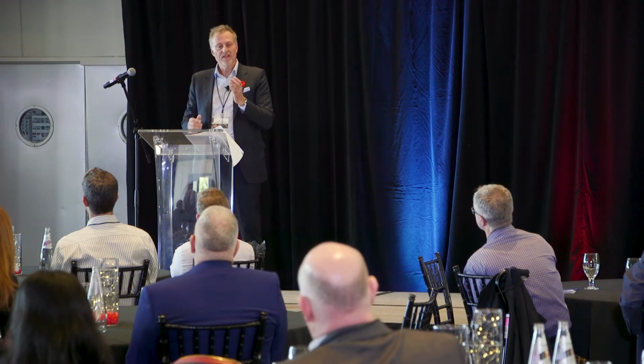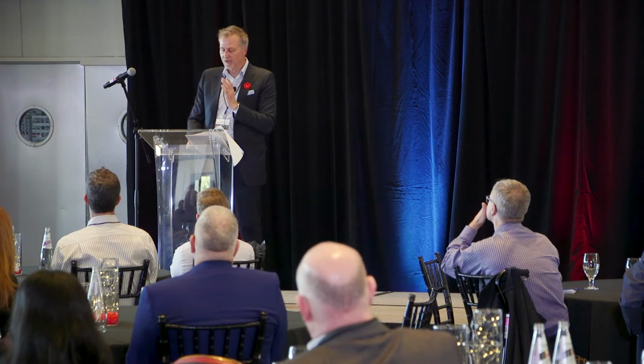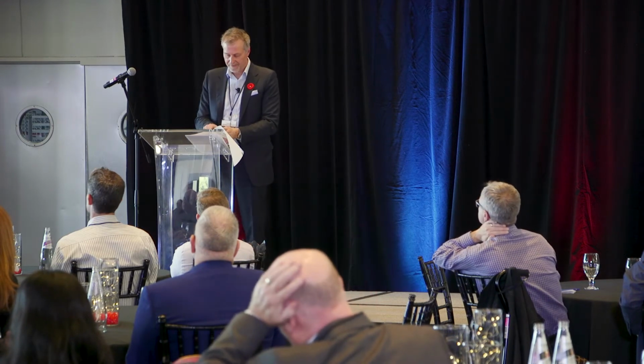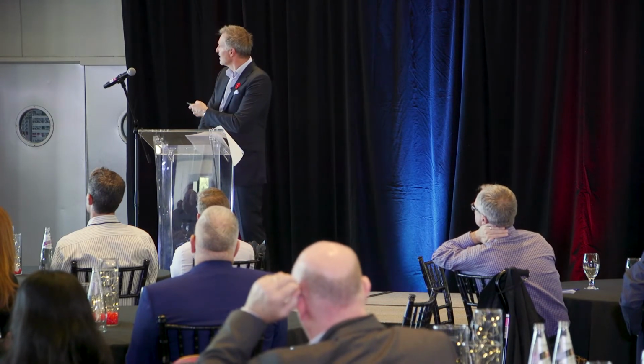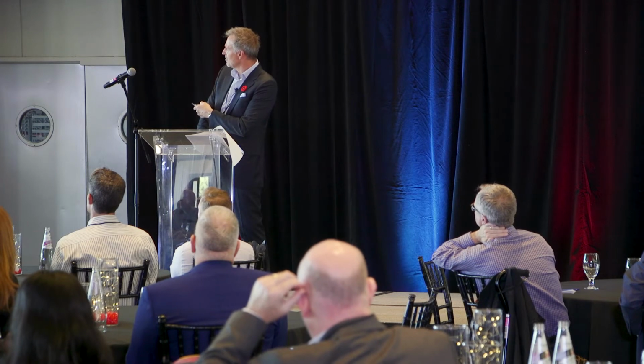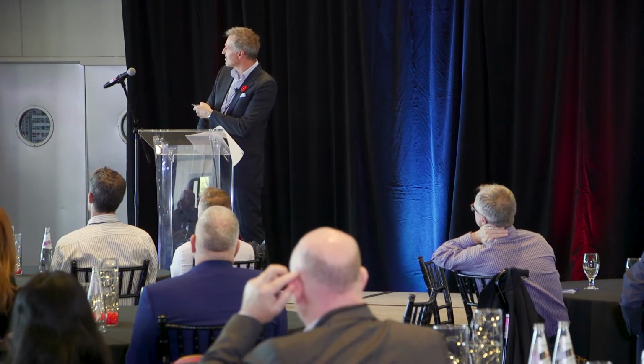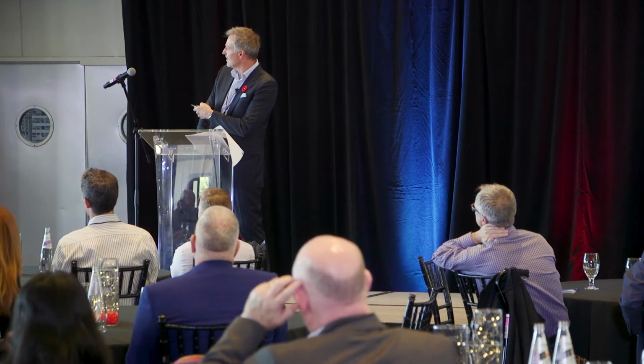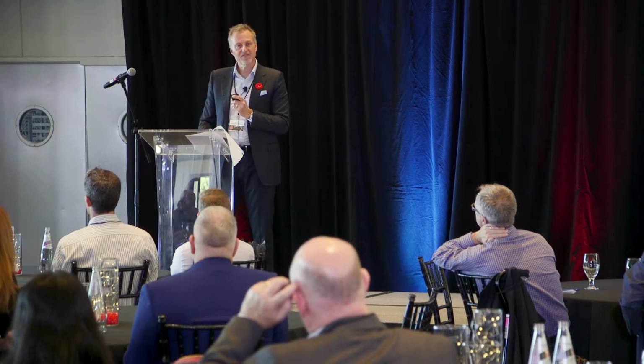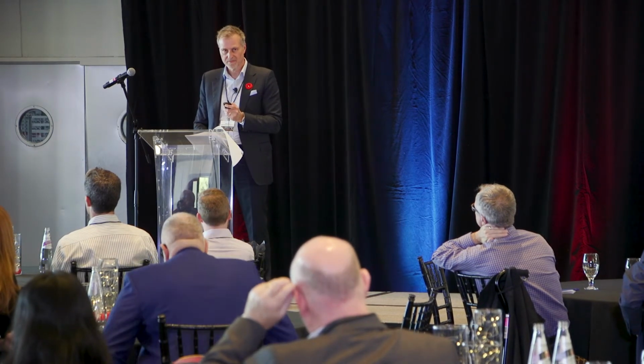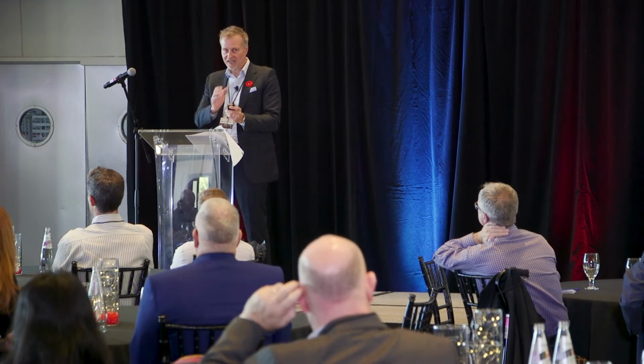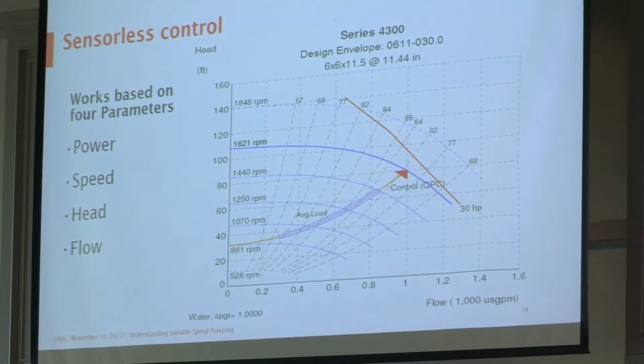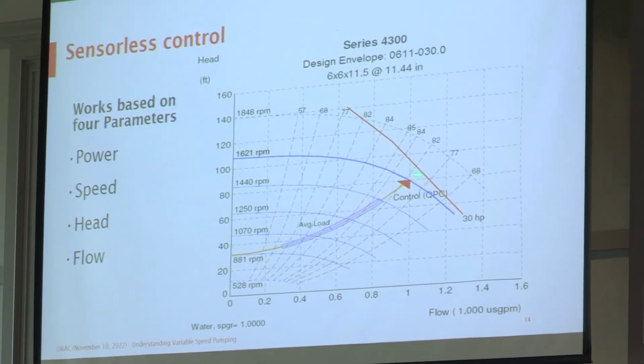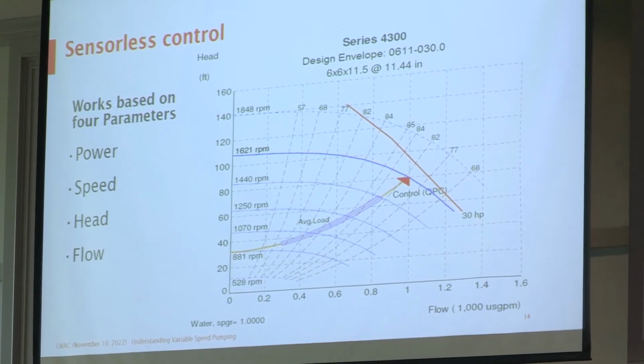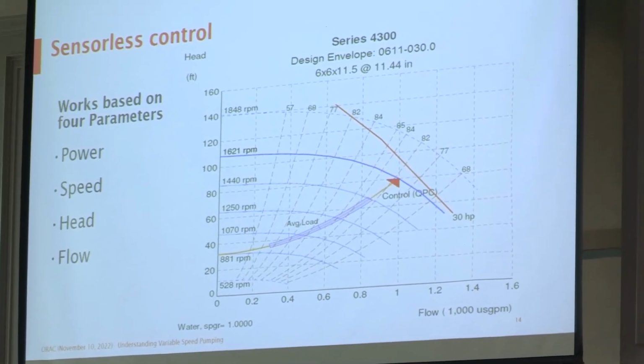So now, historically, if we look at a traditional system, if I have a pump operating at this point right here, and a valve starts closing, I'll start moving up the speed line. If I have a differential pressure switch, it will see an offset on the pressure and adjust the speed accordingly to get back to the control curve, back to a stable situation.